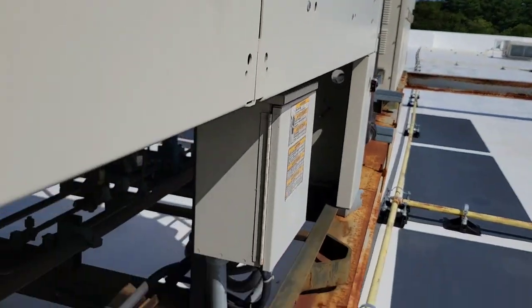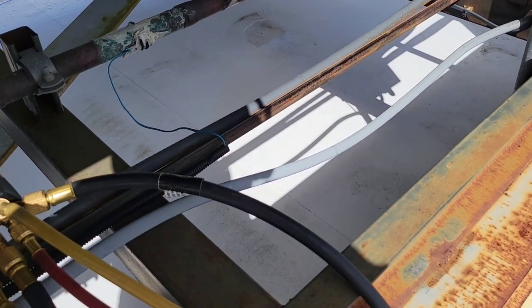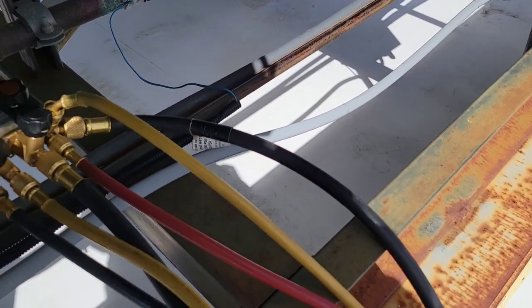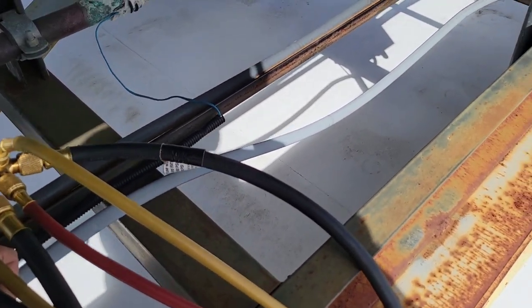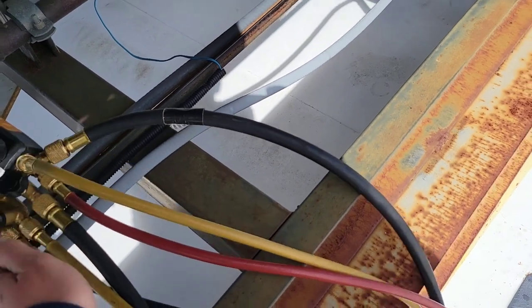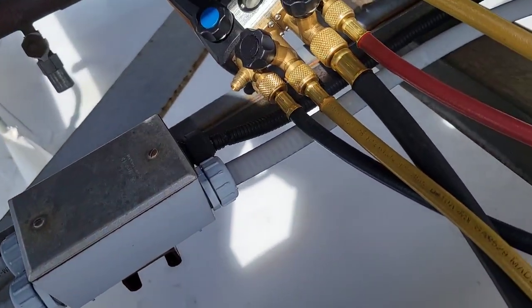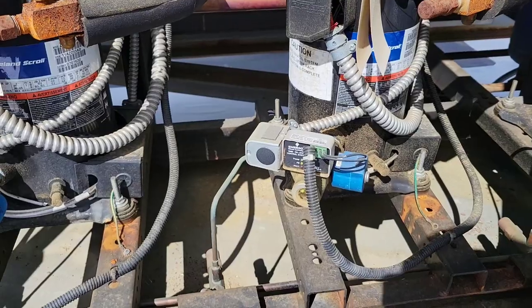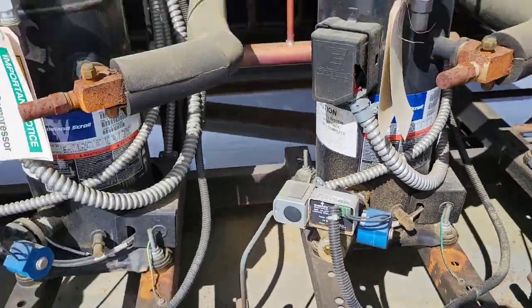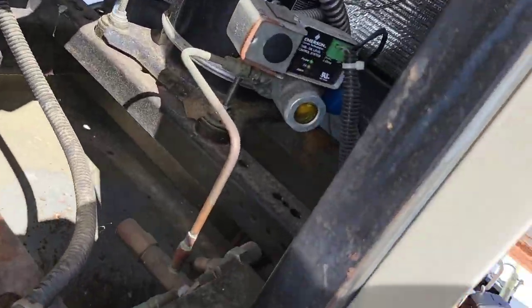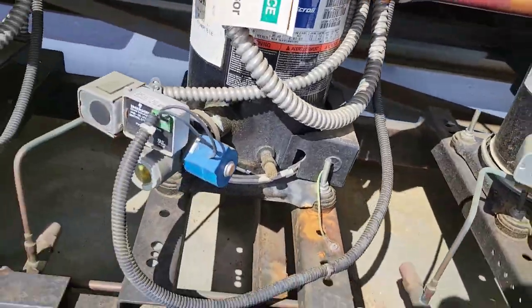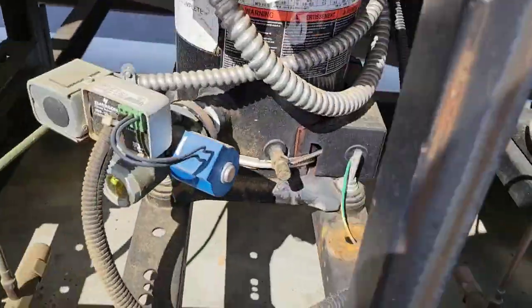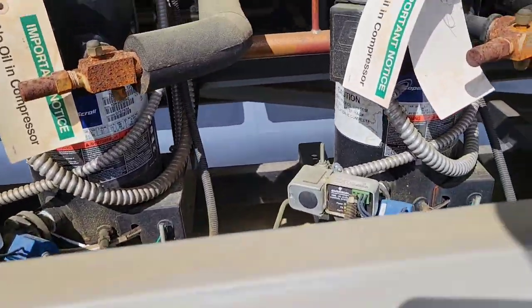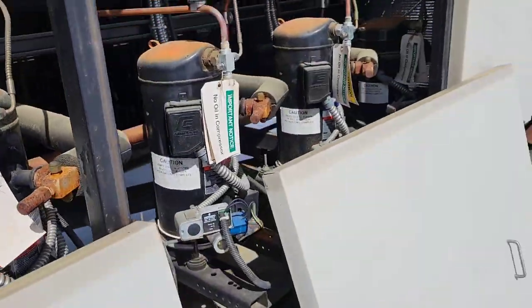So now we're going to move on to the rack. We're going to make sure all the compressors are okay, there's no oil safeties or nothing. And then we're going to move to if there's a CDS valve or solenoid valve. So we're just going to keep going. My pressures are good, so the chance of this having an issue is like nothing, but I just make sure there's no oil failures on any of these things. They're all filled with oil. They look like they're doing okay. So everything looks okay on the compressor side.